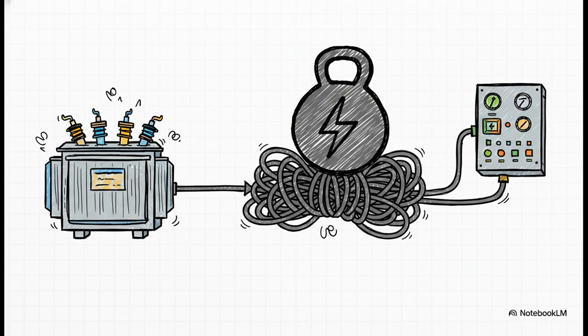So the crucial point here is Rule 4. CT secondary leads must be added to your CT burden calculation. Look, today's modern electronic relays themselves represent almost zero burden. In a lot of cases, the major resistance in the circuit actually comes from the long stretch of copper lead wire running all the way back to the control room. Forgetting to add the resistance of those lead wires is a super common, critical pitfall that will throw your whole accuracy completely out of class.